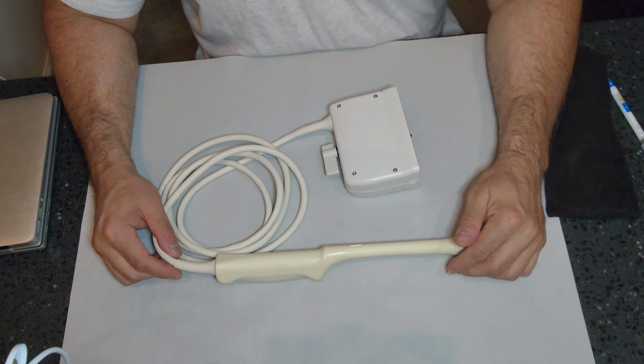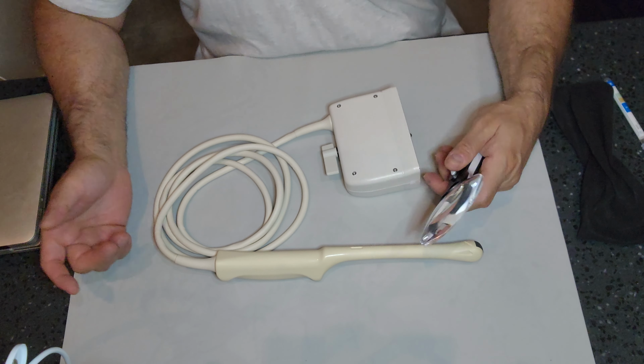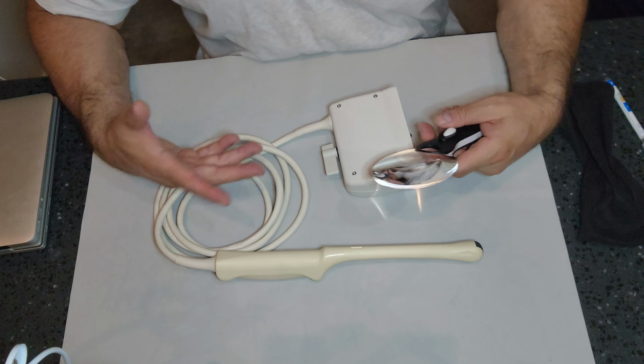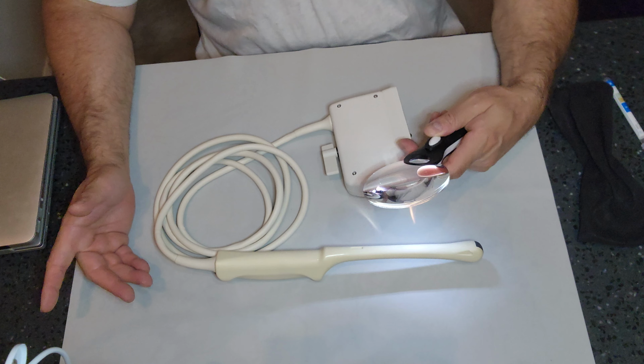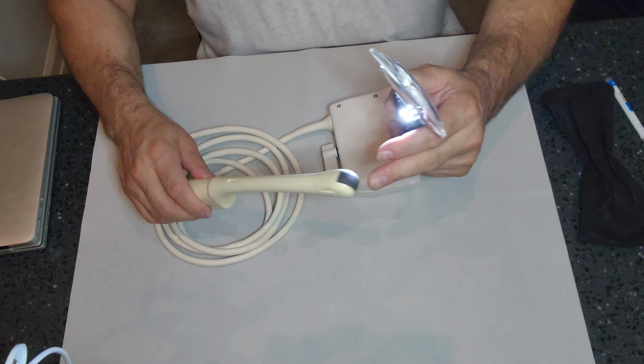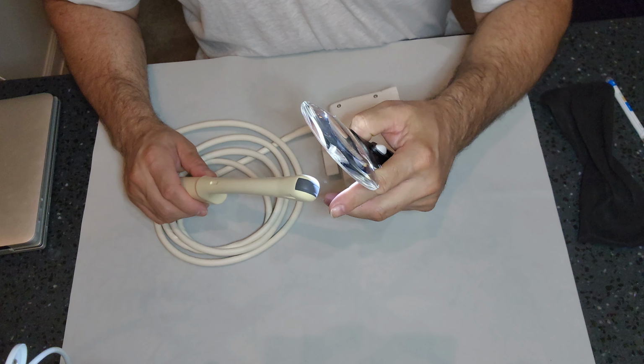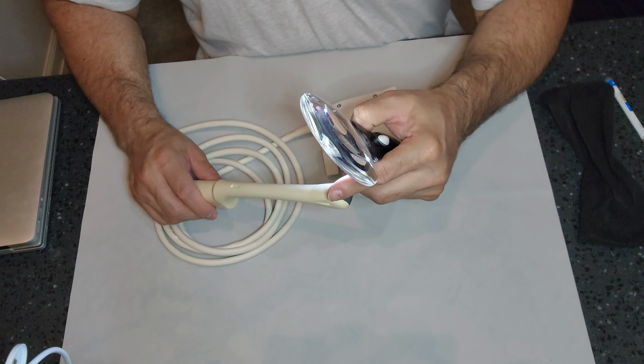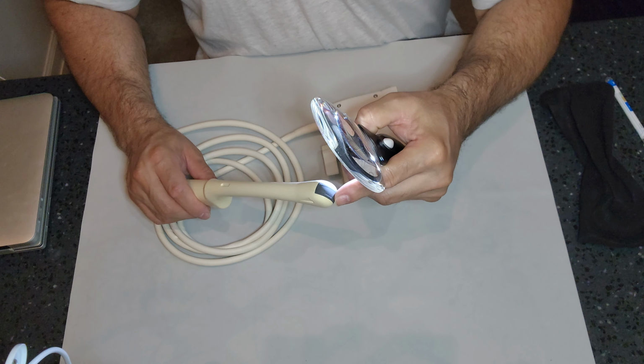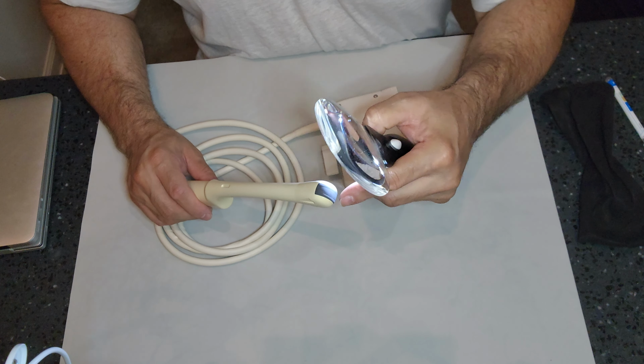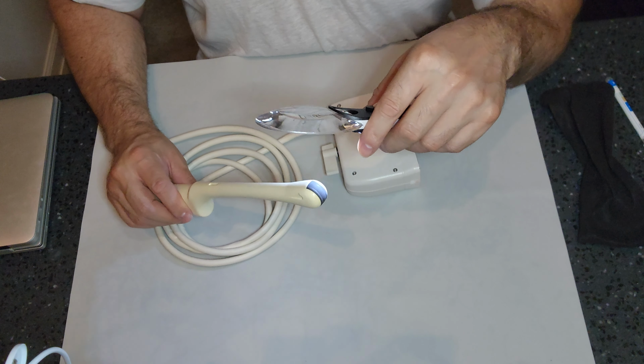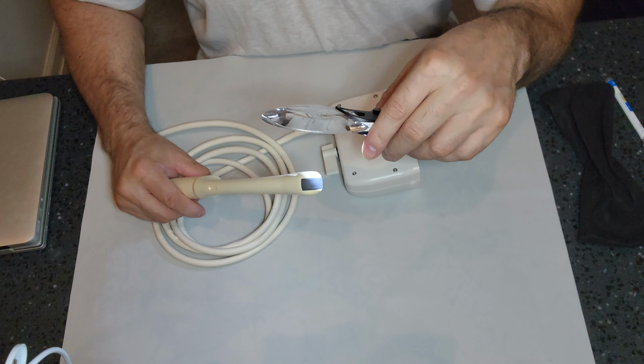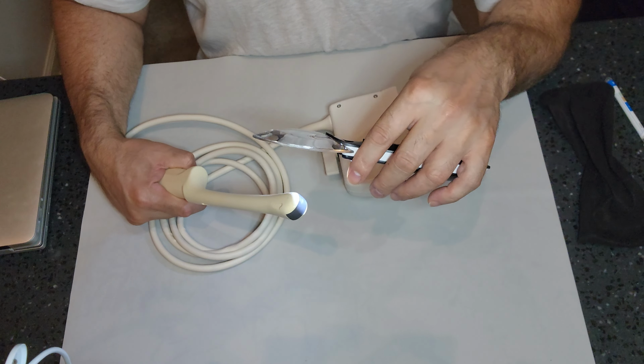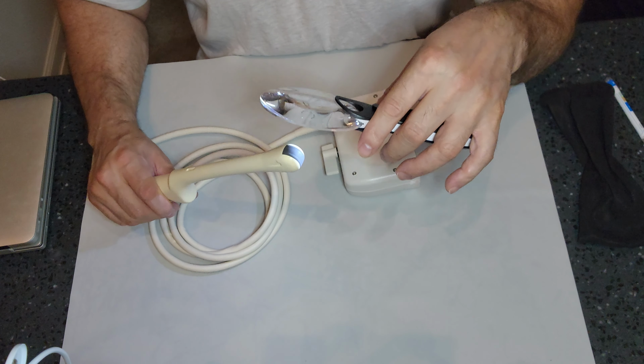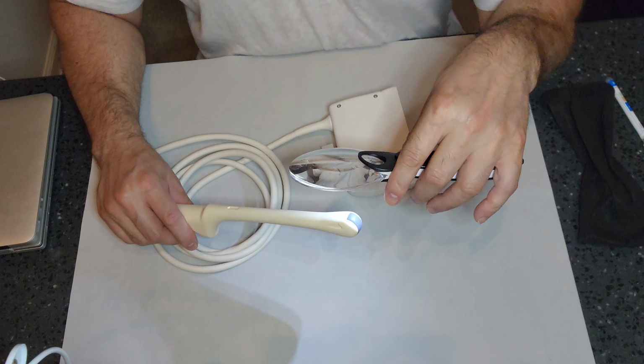So what are we doing? Hey, let's get this lighted magnification out, right? What can we possibly be inspecting on a probe? Come on, really? It's just a probe. Oh, guys, come on. That little distal window right there, that little distal functioning unit of the probe, we want to inspect that for any cracks or breaks or loss of adhesion, because again, if that's damaged, then this probe is no good.